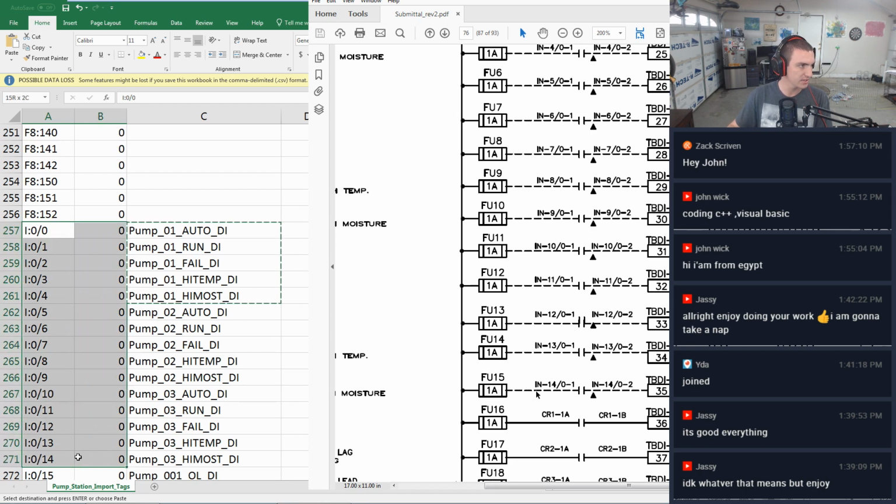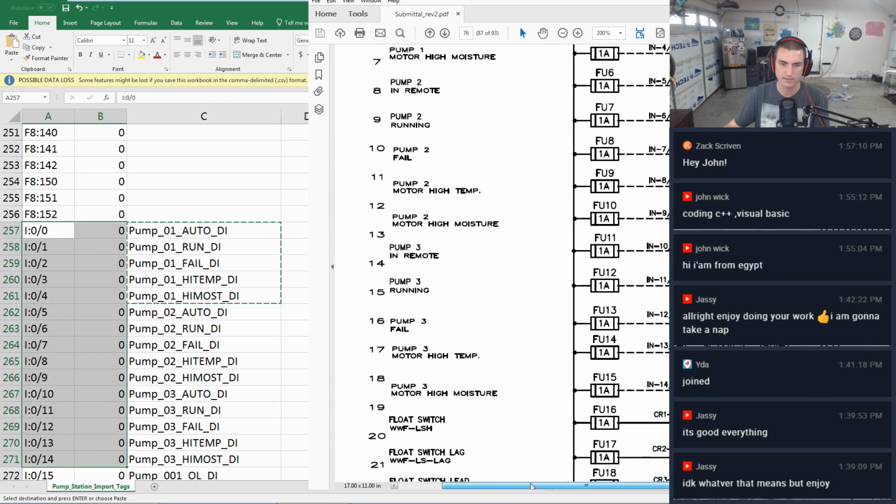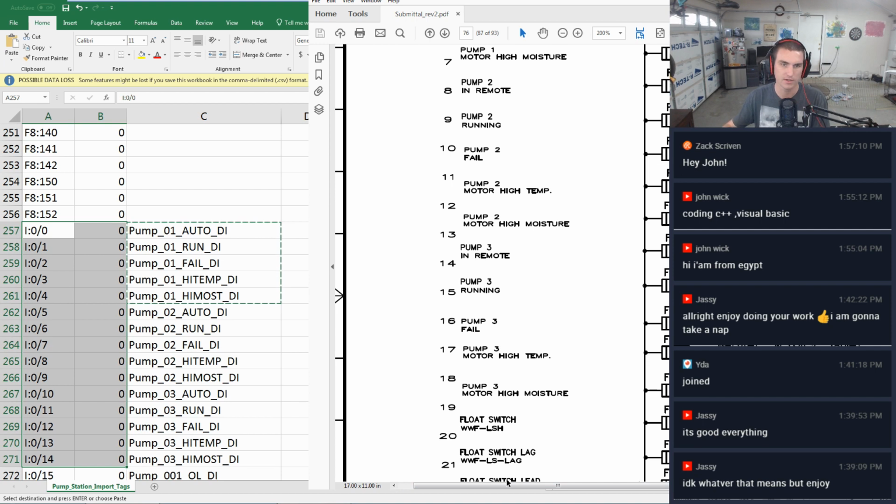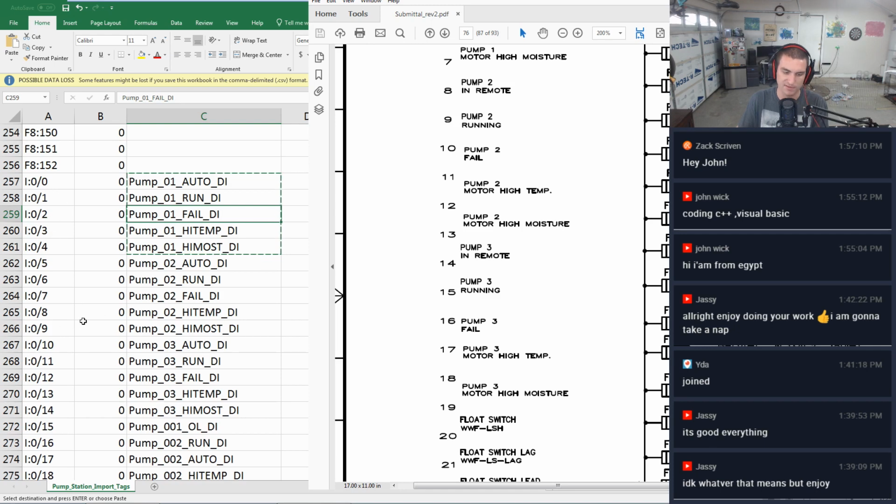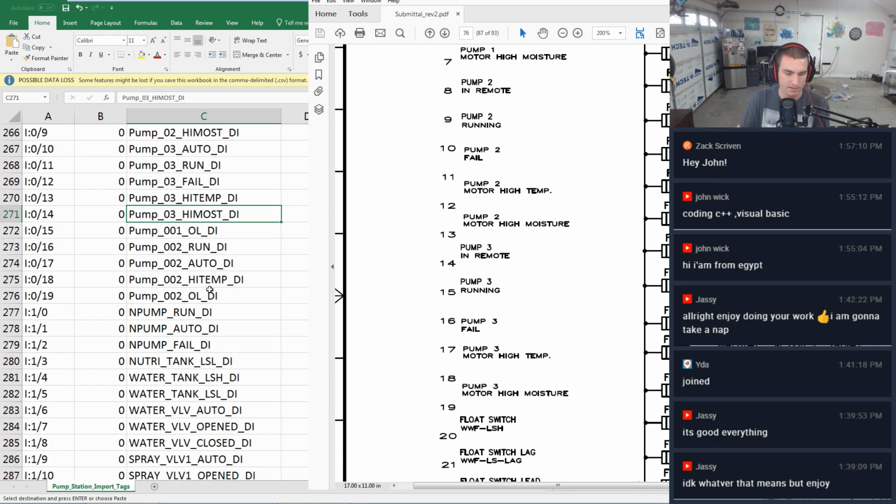Now when I import these within my program, I'll be able to see exactly what those inputs are when looking at them. But basically you never want to really use this physical input address throughout your program. You just want to use that in the mapping routine, map it into your data structure, so then your HMI tagging becomes much more simple and not arbitrary, like 1, 2, 3, 4, 5, 6, 7, 8. Like there's no thought put into that, right?